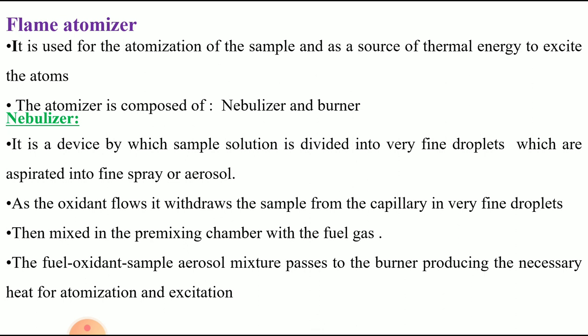The flame atomizer is used for atomization of the sample and as a source of thermal energy to excite the atoms. The atomizer is composed of a nebulizer and a burner. The nebulizer converts the sample solution into fine droplet or aerosol form. By the venturi effect, it withdraws the sample from the capillary in very fine droplets, then mixes it with the premixing burner with the fuel gas. The fuel, oxidant, and sample aerosol mixture passes to the burner, producing the necessary heat for atomization and excitation.